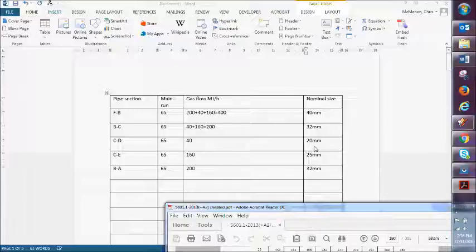the journeyman's exam a while ago, where the gas sizing of an exercise worked out to be 20 mil, and there were blokes about a metre away from the appliance dropping it down to 15 mil, running along at 15 mil to the isolation valve and then to the appliance, and the examiners were saying, you're taking the piss. So the idea was you should be going as close as you can to the appliance.